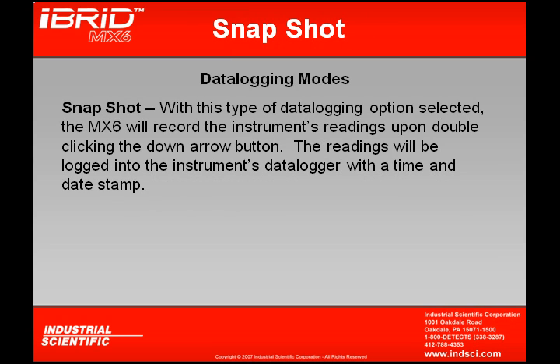The last option for my data logger is Snapshot. With this type of data logging option selected, the MX-6 will record the instrument's reading upon double-clicking my down arrow button. Whenever I double-click my down arrow button with snapshot mode enabled, it's going to take the reading, put it in the data logger, and add a time and date stamp. This is particularly useful for those monitoring VOC release points — rather than continuously data logging, they'll just capture a reading of that VOC release point with a time and date stamp, so when they download, they have those records available.